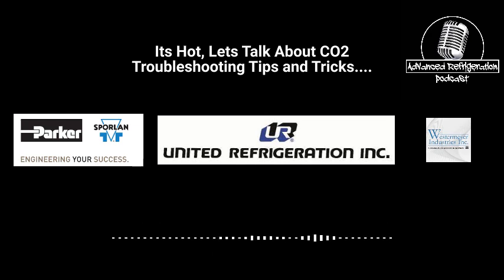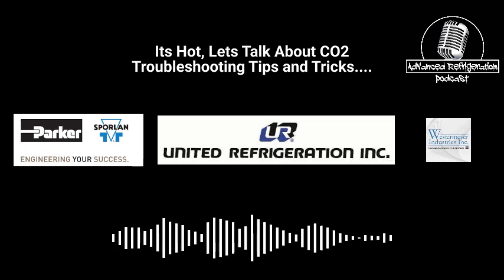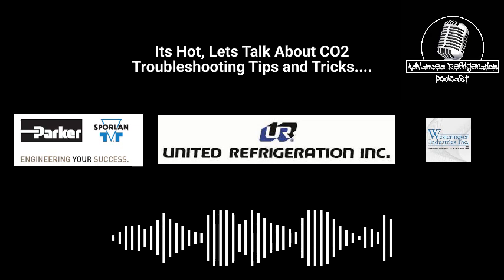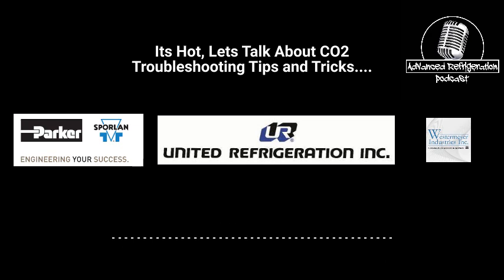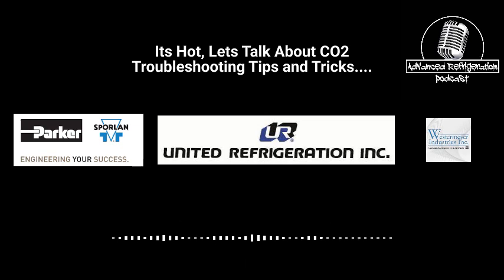Anyway, the BAC ones you've got to be concerned with. I've seen the holes plug up on them on real hard water stores. I've also seen it get wavy, where it somehow ekes its way out and isn't spraying directly where it needs to. We only have one BAC tower. Oh, okay. Most of the time it's just pump problems with hard water. They make a stainless steel version, I guess. They make an upgraded one that's supposed to be a little bit beefier.